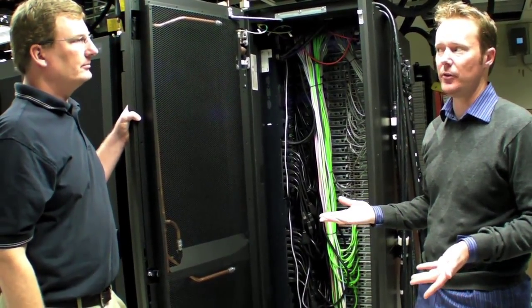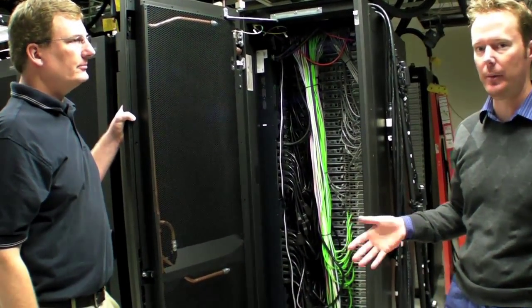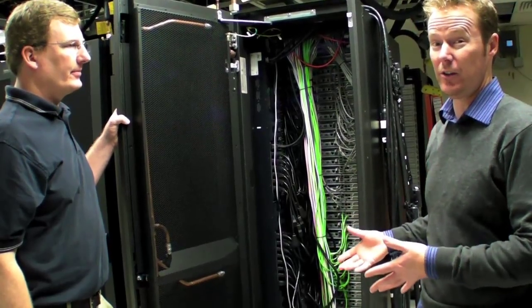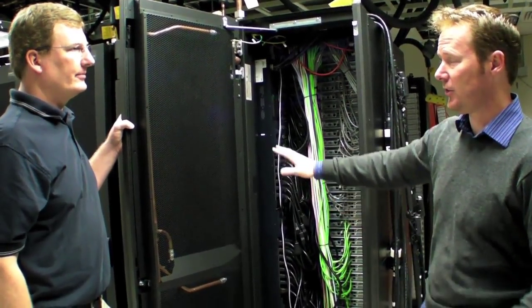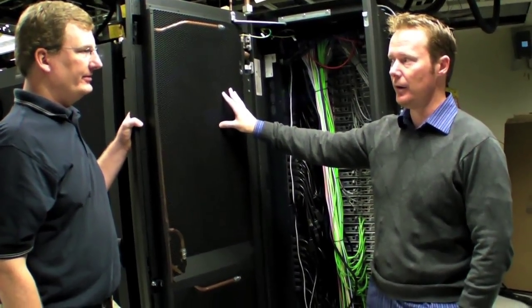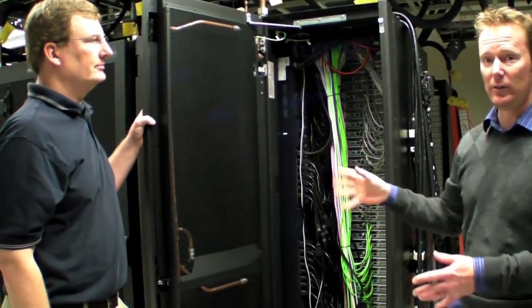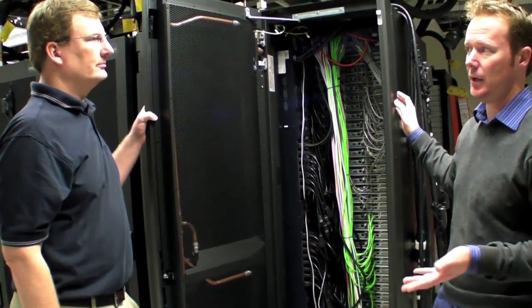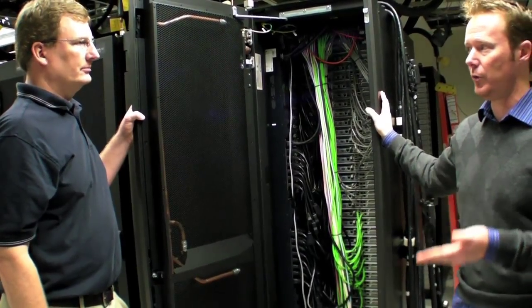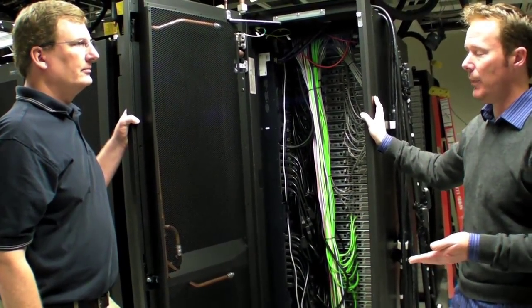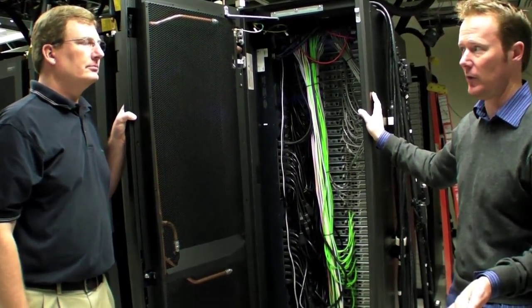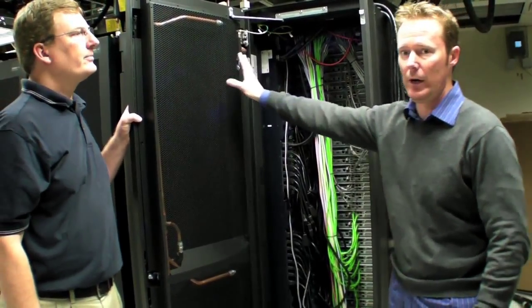That's actually an interesting topic, containment. For years we've been talking about whether to contain the hot aisle or the cold aisle. Your containment is basically built into the rack here. That's right, and not only does that simplify things so we're not spending money on curtains, steel doors, and false ceilings, but you also get the efficiencies inherent in a containment solution built right into the door.